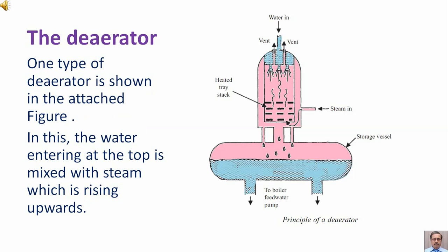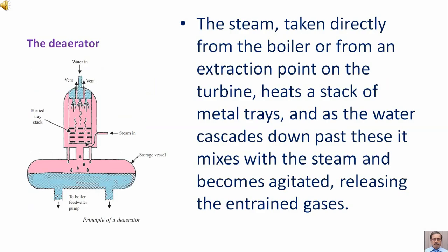One type of deaerator is shown in the attached figure. In this, the water entering at the top is mixed with steam which is rising upwards. The steam, taken directly from the boiler or from an extraction point on the turbine, heats a stack of metal trays, and as the water cascades down past these, it mixes with the steam and becomes agitated, releasing the entrained gases.